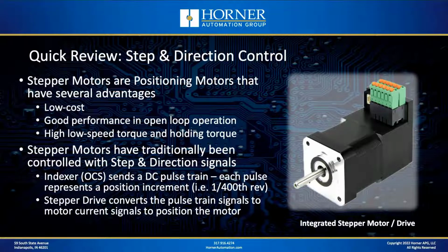Now, traditionally, stepper motors have been controlled with step and direction signals. Today, of course, you can control a stepper motor over a network, maybe with CANopen or with Modbus TCP. But step and direction is the traditional way of controlling a stepper motor, and that's what we're going to include today in our demonstrations. Now, with step and direction, you have an indexer component, and the OCS can act as a stepper indexer. That indexer component sends a DC pulse train where each pulse represents a position increment.